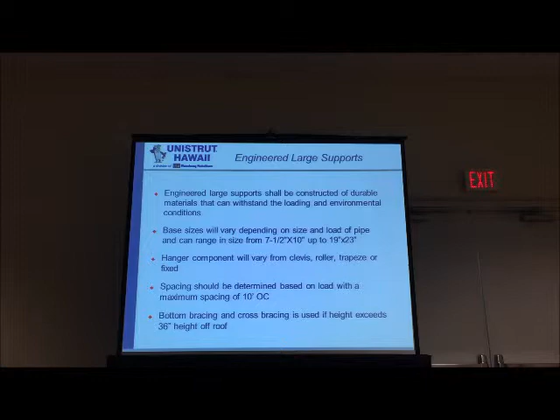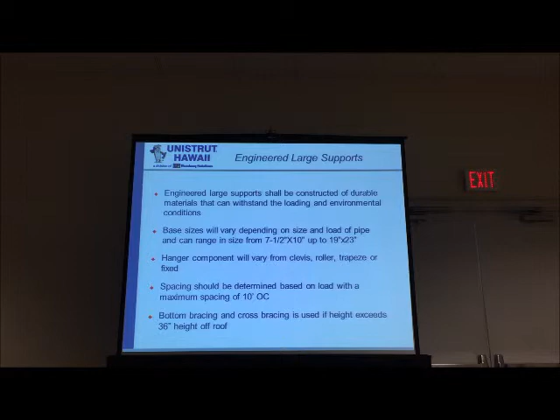But those things don't apply when you're loading your service from the structural steel inside the building. Those kind of parameters don't work on our roof, because we're trying to maintain the integrity of the roof membrane. So maximum spacing should be no more than 10 foot on center, even for large pipe that would typically only require spacing maybe 15, 17, even up to 20 feet.